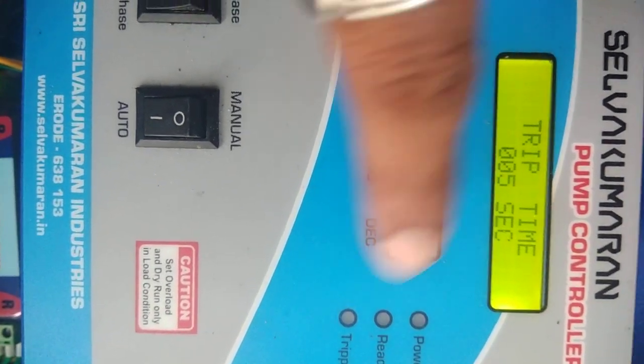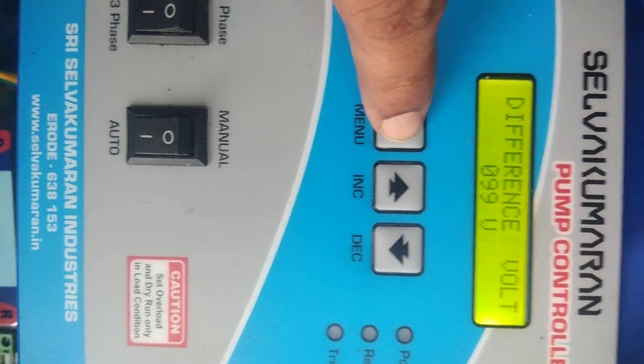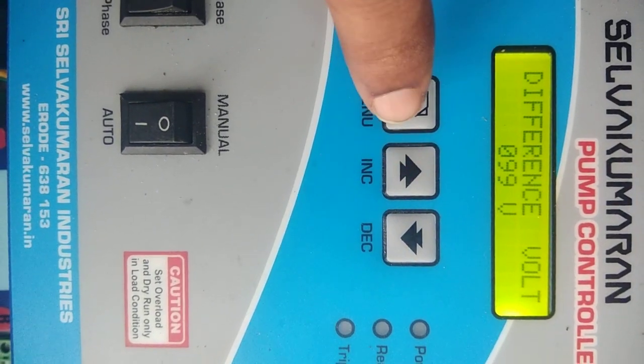Then, trip time. If any problem occurs, the controller will switch off the panel immediately after five seconds. That is for imbalance voltage — if there is any voltage difference between R, Y, B phases, the motor will switch off. The allowed voltage imbalance limit is only 99V.